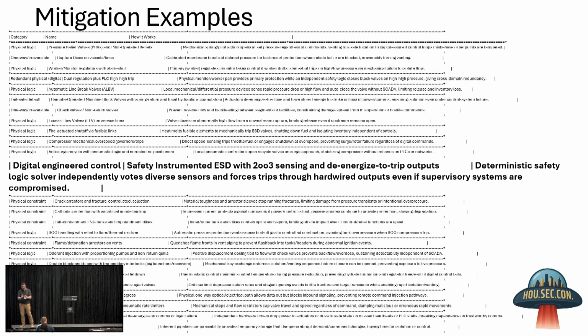I can use a safety technique to remove the consequence a cyber activity might have had if that voting mechanism was not in place. Because without that voting mechanism, the sensor, let's say a flow sensor, is being used as the input signal to the unit control or station control to decide how much volume needs to flow through the system.